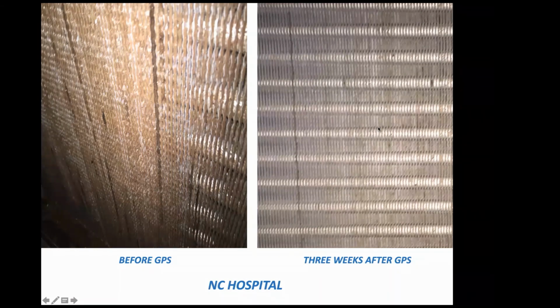We did a hospital out in Alabama that had over 4 inches of pressure drop, and we took the 4 inches down to 1 inch over a period of 6 months. It was a really packed coil. They were about to just replace it. And we said, if you can work with us, we'll give you the system. Let us get the data. So it went from 4 inches to 1 inch over 6 months.